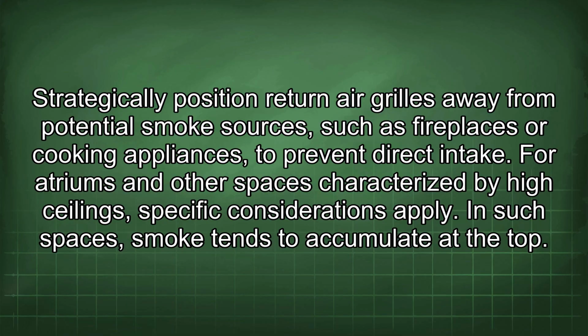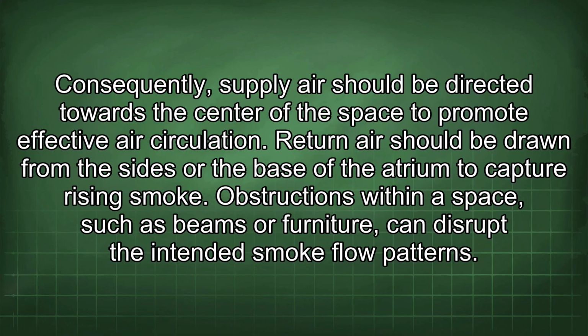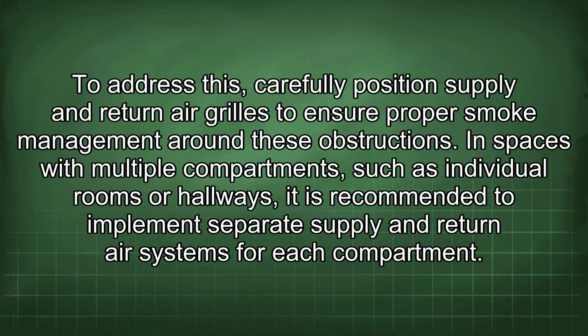In such spaces, smoke tends to accumulate at the top. Consequently, supply air should be directed towards the center of the space to promote effective air circulation. Return air should be drawn from the sides or the base of the atrium to capture rising smoke. Obstructions within a space, such as beams or furniture, can disrupt the intended smoke flow patterns. To address this, carefully position supply and return air grills to ensure proper smoke management around these obstructions.